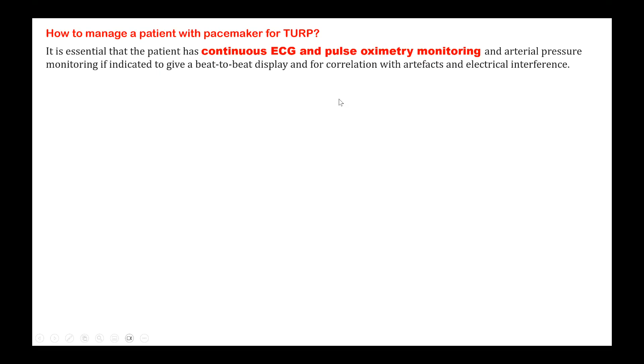So what type of pulse oximeter monitor should you use in these patients? Is it enough if you get a saturation value? You should have a plethysmograph also present in the pulse oximetry. And the ECG monitor should be set at diagnostic mode, not on the regular display mode. It should be able to diagnose any arrhythmias or any artifacts. So you set the ECG on diagnostic mode so that the pacing spikes can be appreciated. And the use of bipolar cautery instead of monopolar is preferred. And the electrosurgical return plate should be positioned so that the current pathway does not pass near the pacemaker.